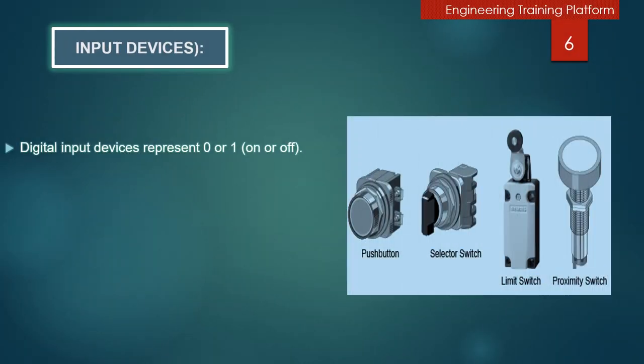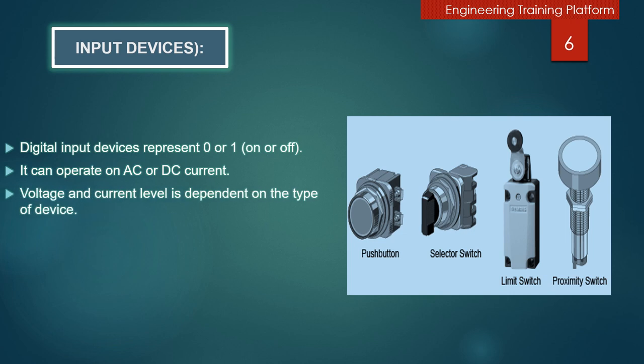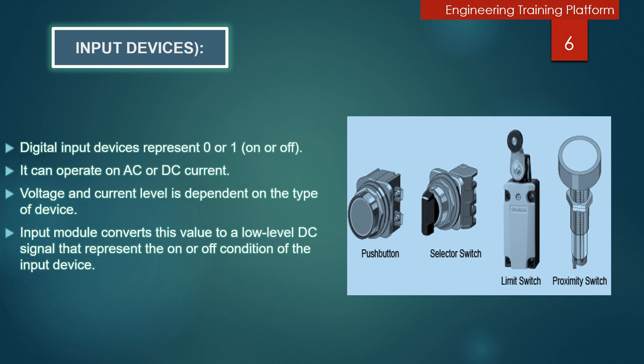Digital input devices such as push buttons, selector switches, limit switches, proximity switches which are shown in the picture. Digital input devices represent 0 or 1. They can operate on AC or DC current. Voltage and current level depends on the type of device. Input modules convert these values to a low-level DC signal that represents the on or off condition of the input device.